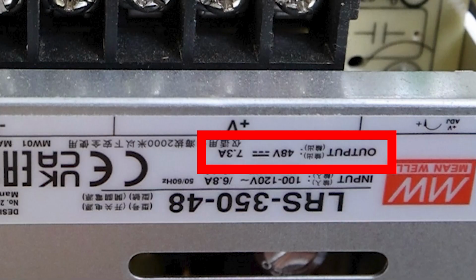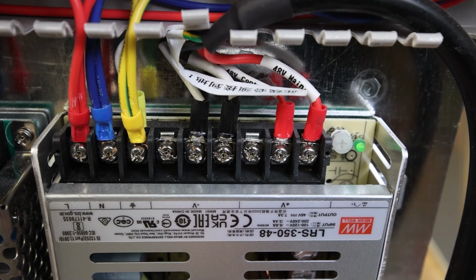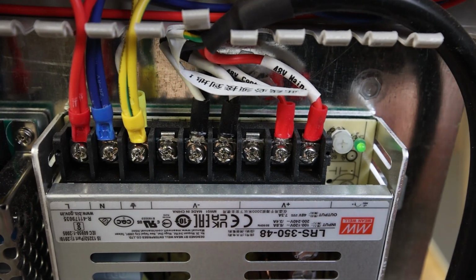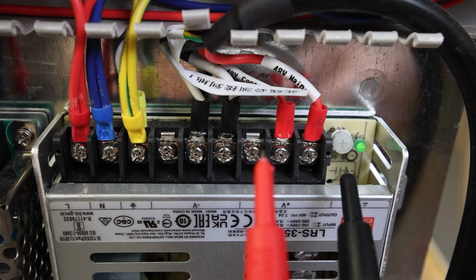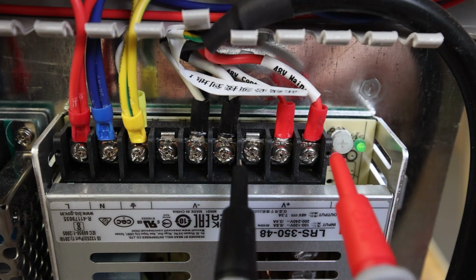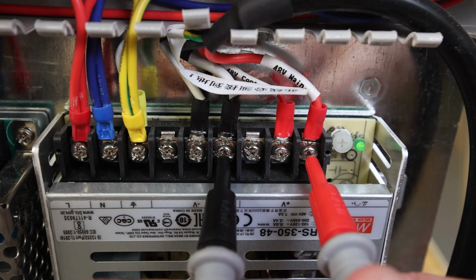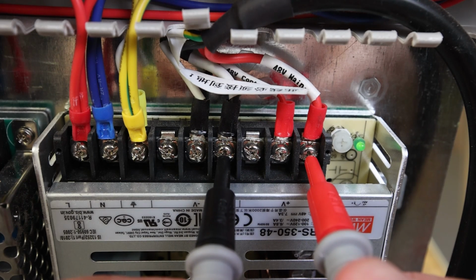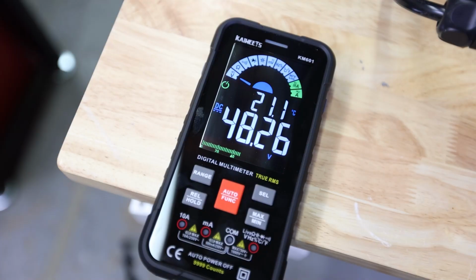It lists an output of 48 volts at 7.3 amps, so this should be the unit supplying power to our laser source. When testing, we want to place the red voltage probe on one of the 48 volt terminals and the black common probe on one of the negative voltage terminals. If the power supply is functioning correctly, we should get a reading of 48 volts.